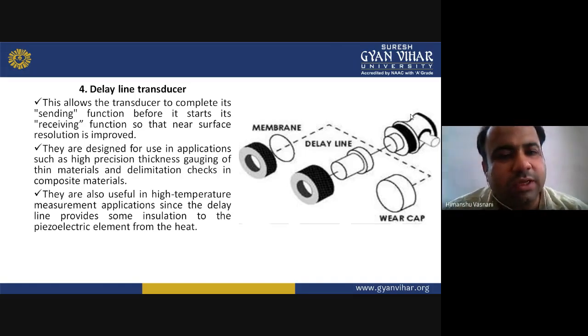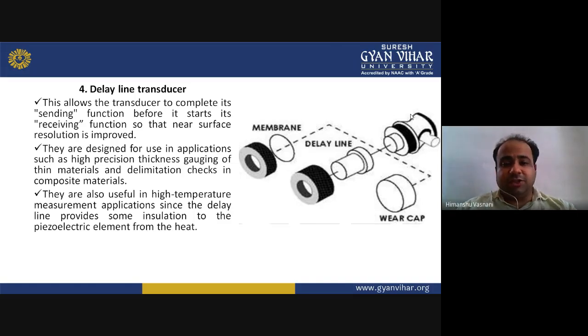They are designed for use in applications such as high precision thickness gauging of thin materials. The previous transducer was also used for measuring thin materials, but here it is used for high precision thickness measurement and delamination checks in composite materials. So this has precision in it. They are also useful in high temperature measurement applications, since the delay line provides some insulation to the piezoelectric element from the heat. They are protected from the heat.